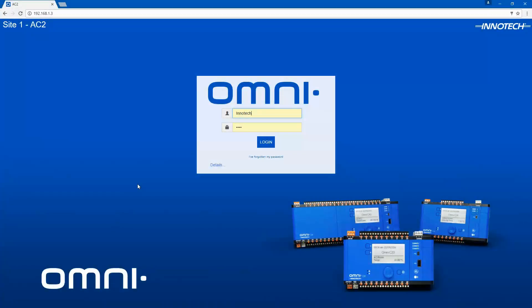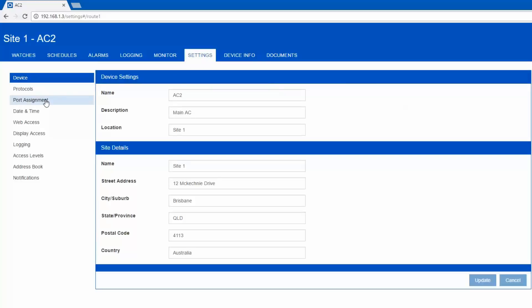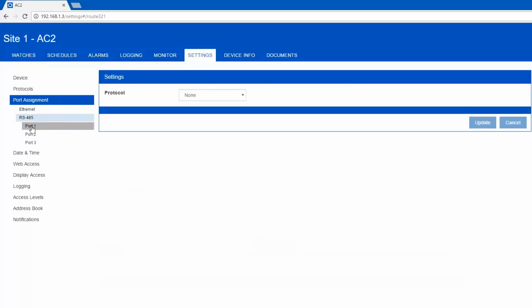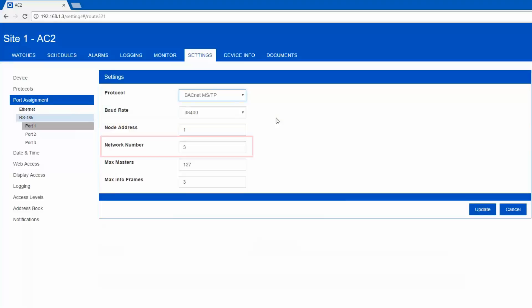Log in to the controller and navigate to the settings and port assignment menu. Access the RS-485 menu, then select the port to be configured. Under the protocol list, select BACnet MSTP. Check and adjust the baud rate as required. In this case, my device requires 38400 baud. Also check and adjust the network number if required. The default for an Omni comm port is 3. This will need to be changed if network number 3 is already in use.